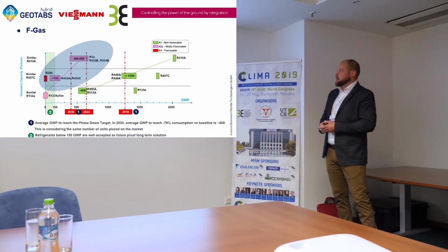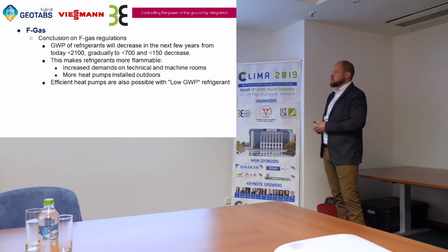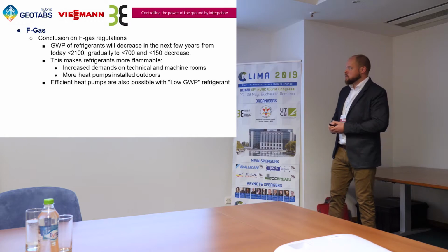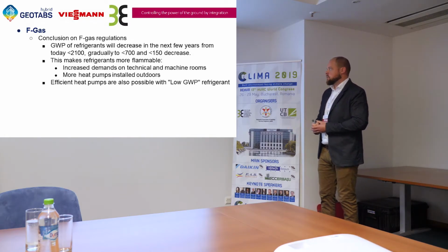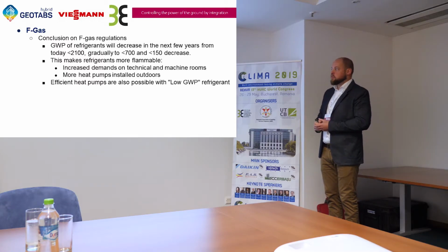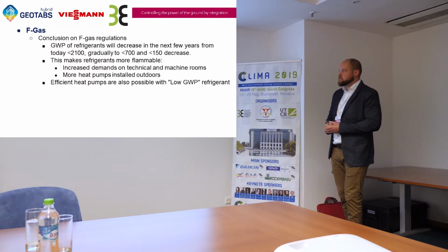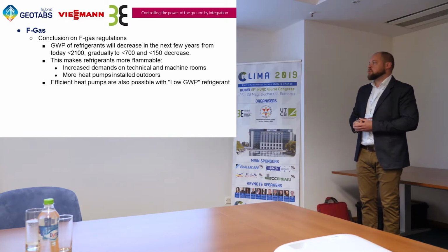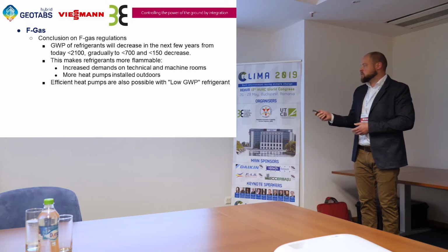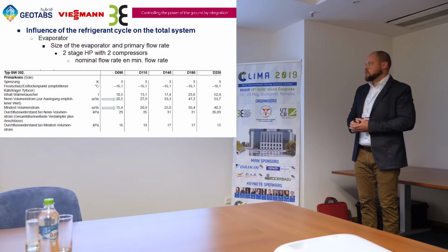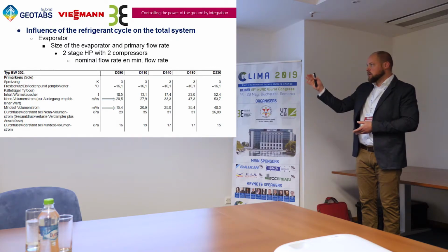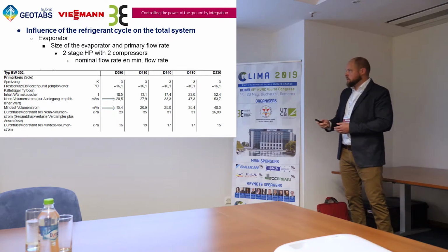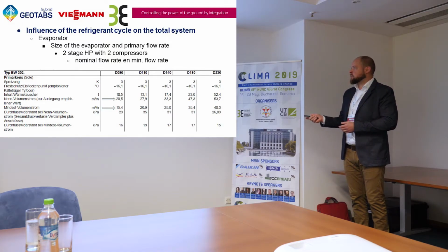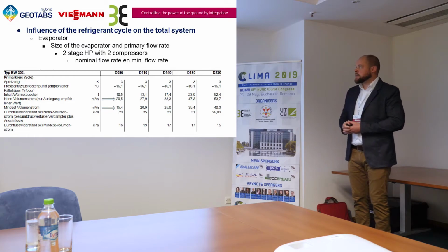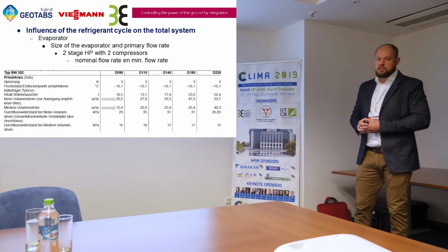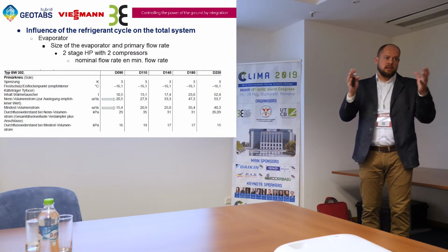So a conclusion on the F-gas regulation is that the GWP has to decrease. It will decrease gradually. Today, less than 2,100, and in the future, less than 700, and even less than 150. This makes refrigerants more flammable, so there are increased demands on technical and machine rooms, and more heat pumps will be installed outdoors. Efficient heat pumps are also possible with low GWP refrigerants if you have the right components inside the machine. Here again, a table from the heat pumps we sell. We have different output powers, from 90 kilowatts going up to 230. We see that all these machines work with two-stage compressors, which means we have two compressors in one refrigerant cycle.